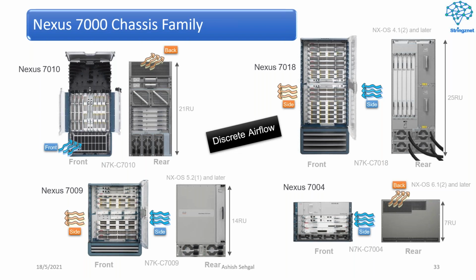Why Cisco? Because Cisco thought of adding certain fancy components into it, locking the switch with the help of a glass door. If you are putting a glass door in front, of course, the glass door will hinder the air. Definitely, the glass doors are removable. And if you go into any data center using 7000 series of switches, nowhere will you get an opportunity to see the glass door being used. Why? Because it is definitely going to impact the temperature of the chassis.